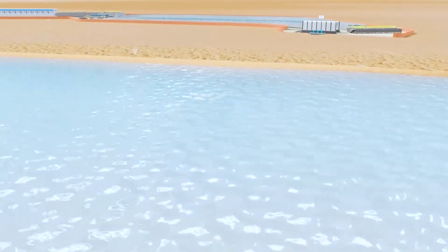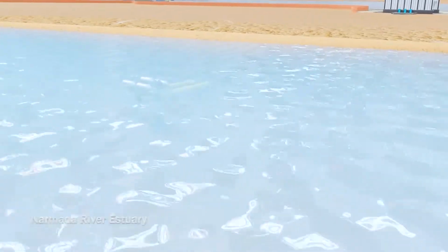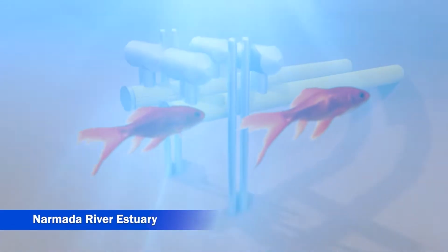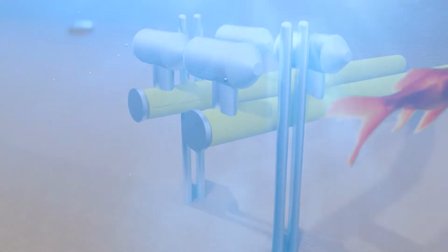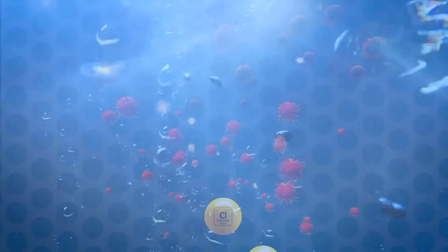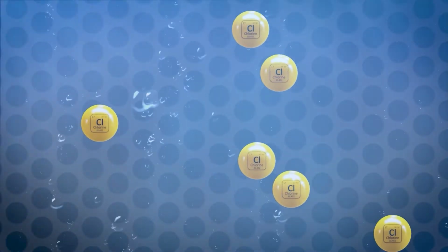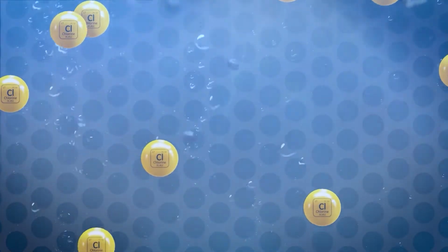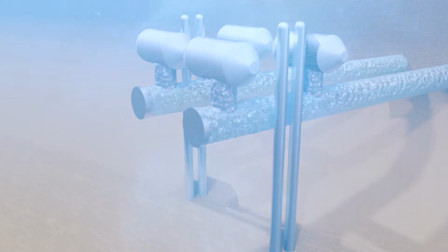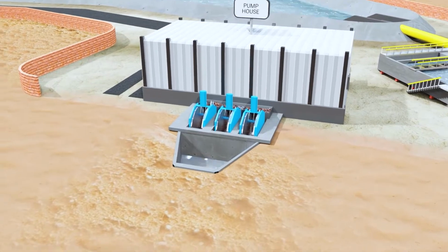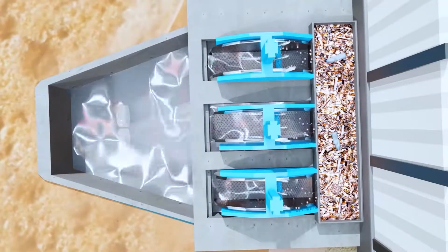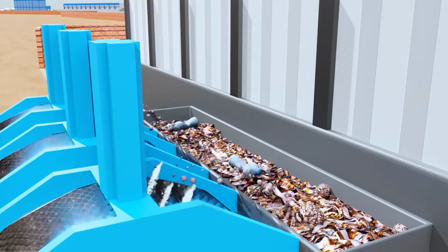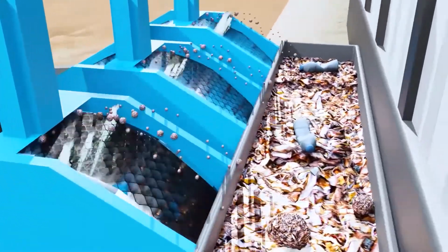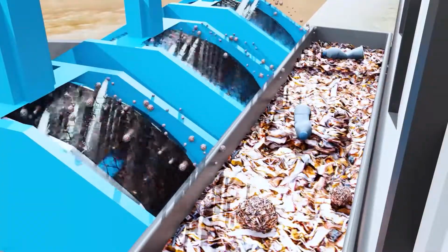Initially, at the time of high tide or low tide, water will be raised into the reservoir from the Narmada River estuary through 4 perforated intake screens. Inside the intake screen, chlorination will occur with the help of a chlorine dosing system to prevent marine growth inside the intake system. From the river, water will move to the pump house through the 1800 DIA underground twin HDPE pipeline by gravity. In the pump house, water will enter the travelling band screen chamber through inlet chamber, where large unwanted particles inside the water will be eliminated by a continuously rotating screen.